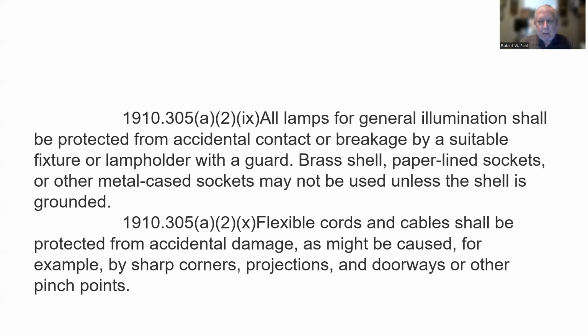All lamps for general illumination shall be protected from accidental contact or breakage by a suitable fixture or lamp holder with a guard. Brass shell, paper lined sockets, or other metal case sockets may not be used unless the shell is grounded. Flexible cords and cables shall be protected from accidental damage, as might be caused, for example, by sharp corners, projections, and doorways or other pinch points. That's something when you're walking through a place you want to look out for. Flexible cords, people will run them anywhere.